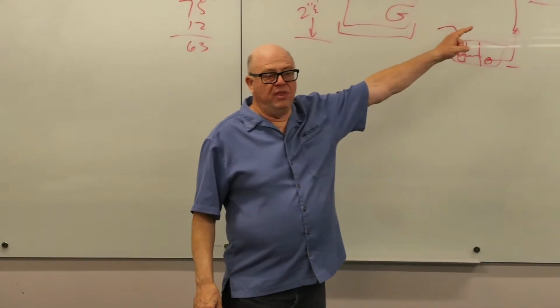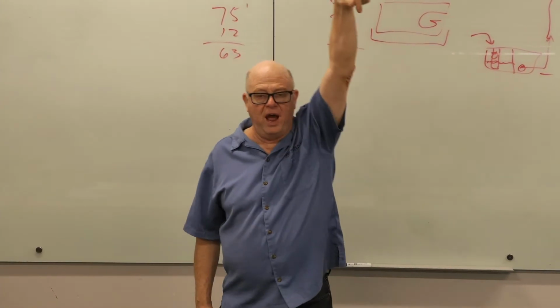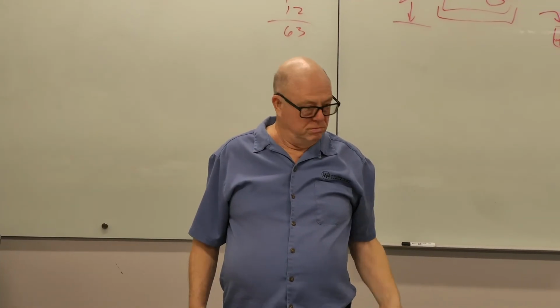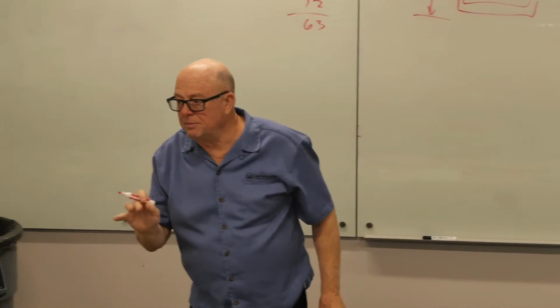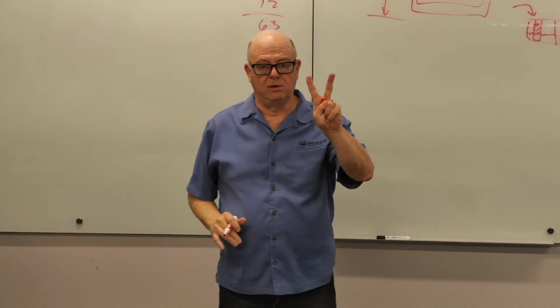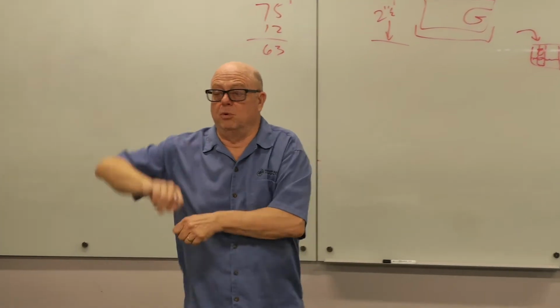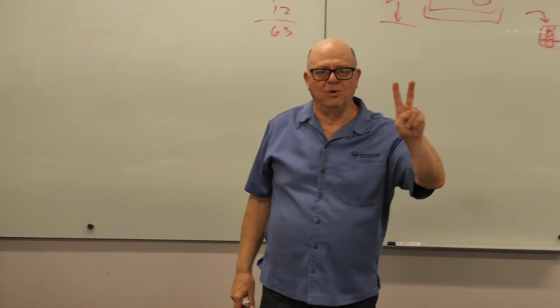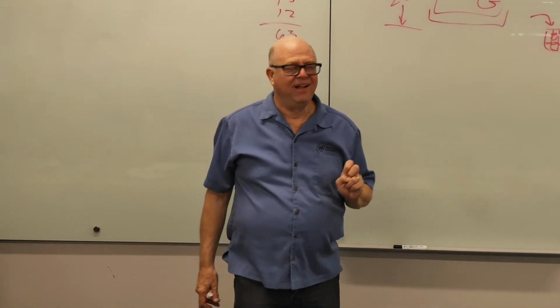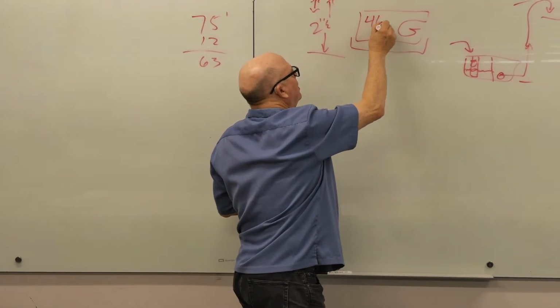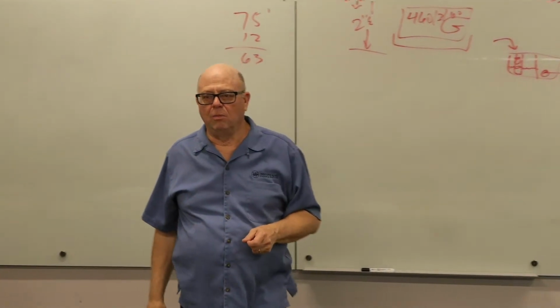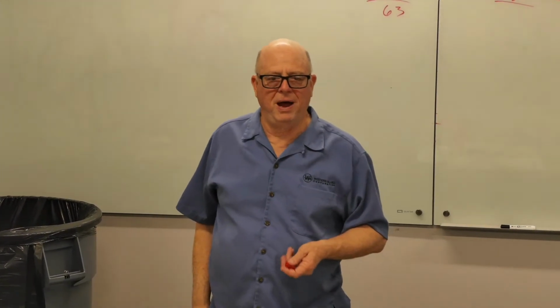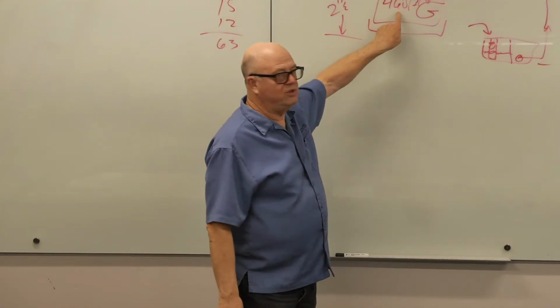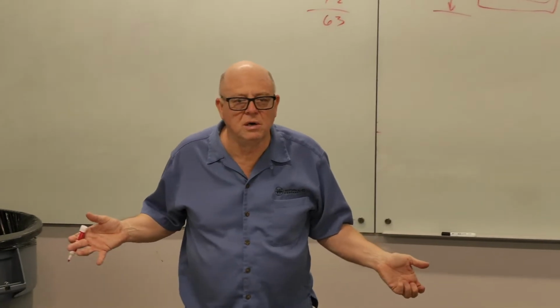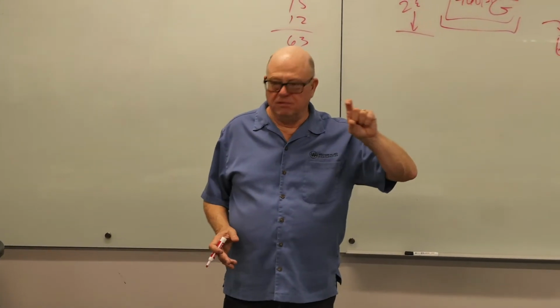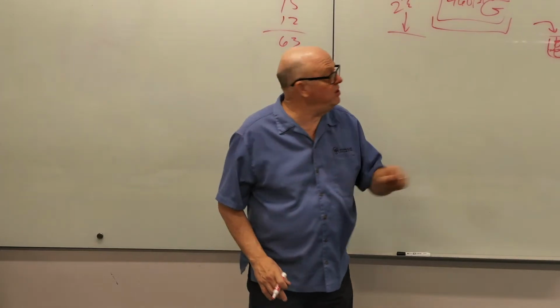But what if you're on the second floor and you're trying to get it up through the third floor and out into drains on the roof? Well, now you need more feet of head, right? So anytime you buy a condensate pump, there are two things you've got to know. The first is how many feet of head, and will that work for wherever I'm taking the water. The second thing you need to know is the voltage. If this is a 460 volt water source heat pump, there will be a control power transformer in there, and it's a very good chance it goes from 460 to 24 volts, because that's what your controls are using. Will there be enough extra VA, volt amps, that's how they rate these, right, to power the condensate pump?